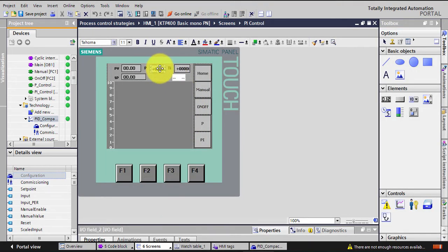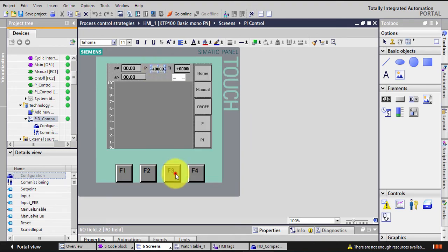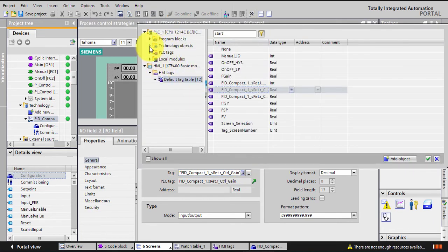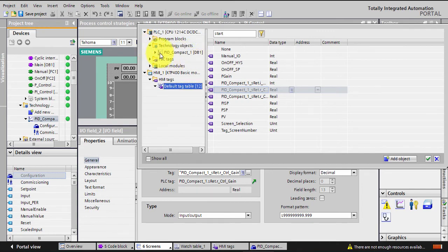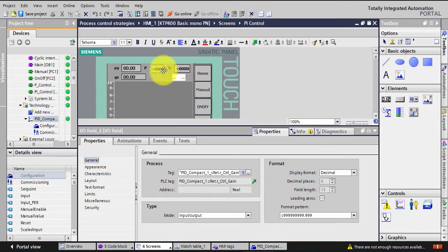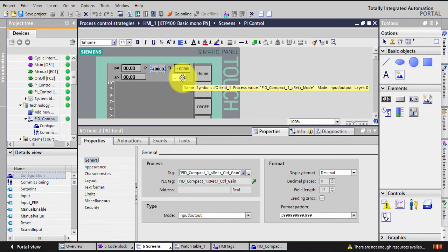In the HMI, this is where the proportional gain and the integral action gain are displayed. To link them, I right-click, go to Properties, then Tags, and navigate to the Technology Object. I find the PID Compact I added in the cyclic interrupt and link the proportional gain, the actual integration time, and the actual derivative time — if using D. This allows me to manually enter and change those values to tune the PID. I also create a text field to turn the PID on, since this is Compact version 1.